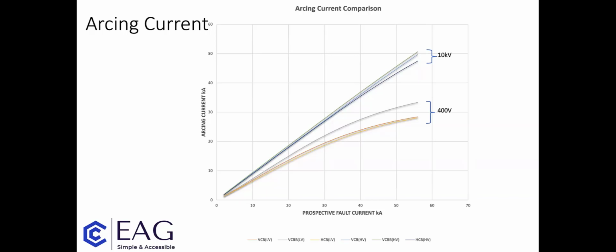At high voltage, the attenuation is very much less than at low voltage. And you can see in the graph here, it shows the arcing current against prospective short circuit current for 3 different electrode configurations. Firstly, for a 10 kV system, popular in Europe, 11 kV generally seems to be the distribution voltage in the UK, and 400 volt system voltages, which is harmonized across Europe. Whilst you're extremely unlikely to experience fault levels of 50,000 amps on 10 kV or 11 kV systems, it just serves to make a comparison, I think.